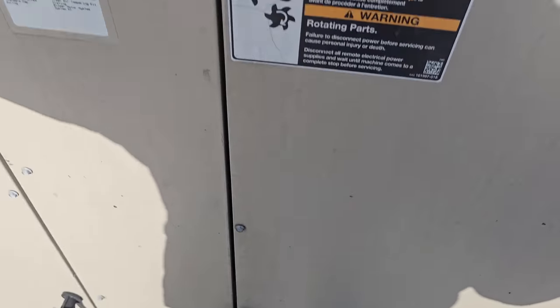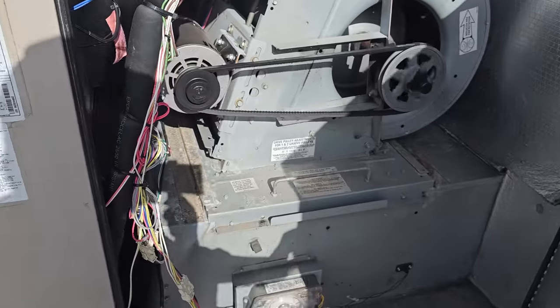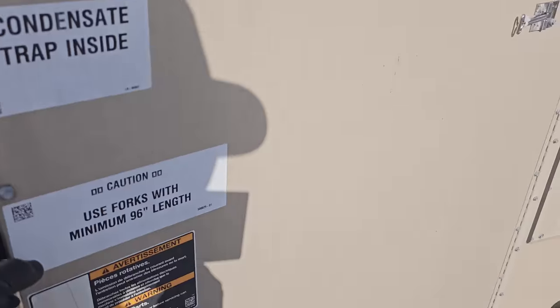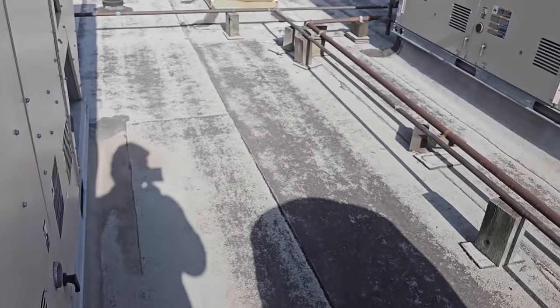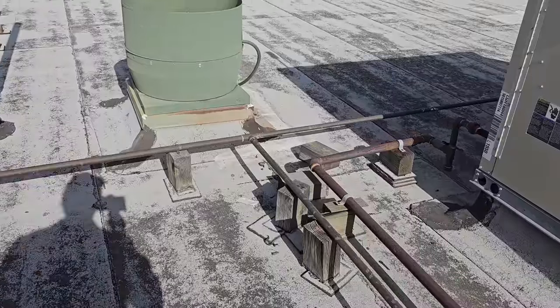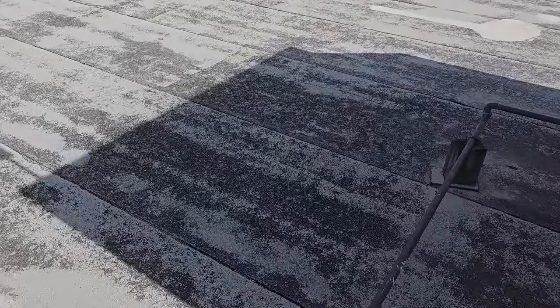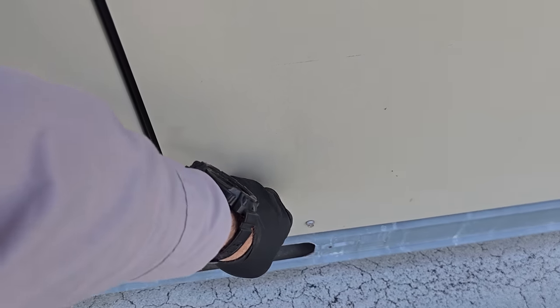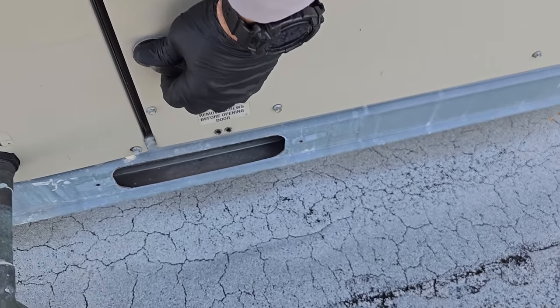Ugh. So they use a national filter changing company here. That one's got a loose belt too. You can tell that it's loose on the bottom. So we got lots of... So all you got to do is open your eyes. Look, these customers don't do routine maintenance. But if I'm here, I'm going to look. Now, I'm not going to spend my day here maintaining all their equipment.